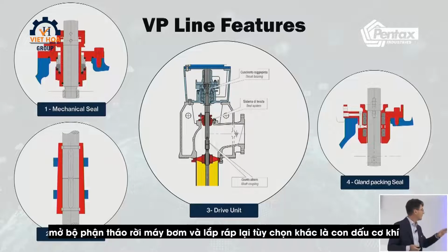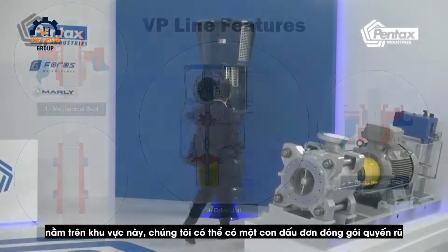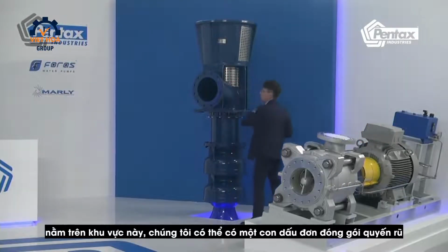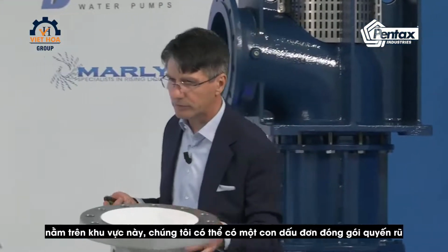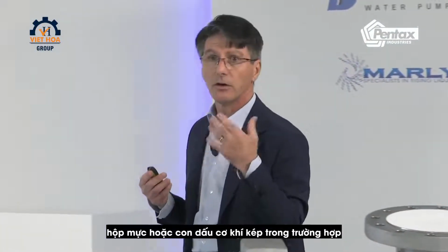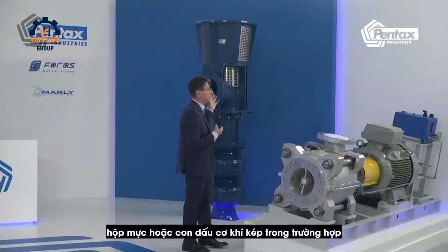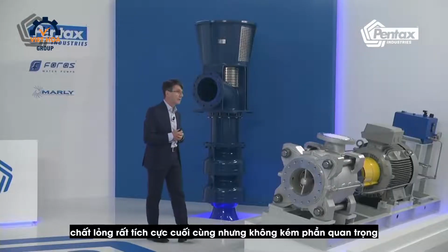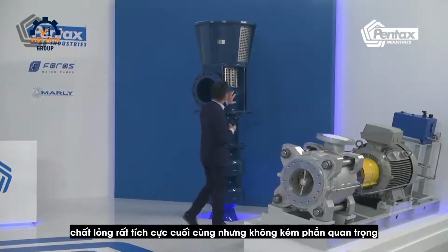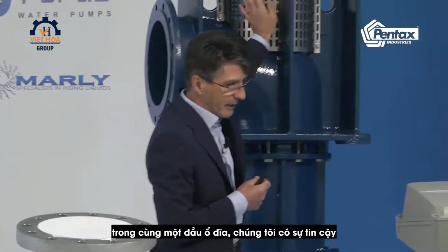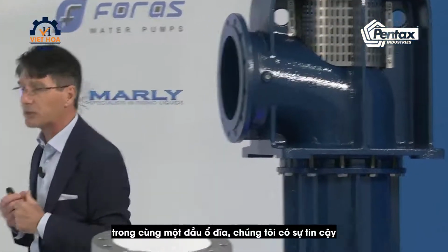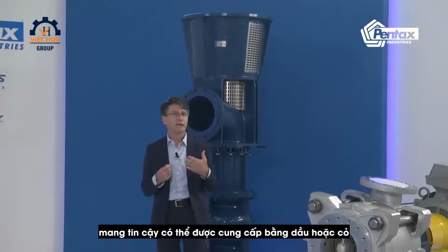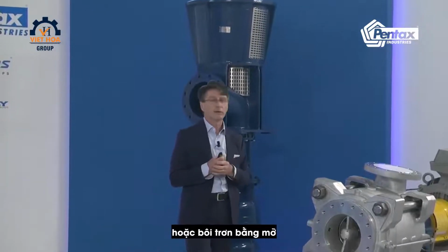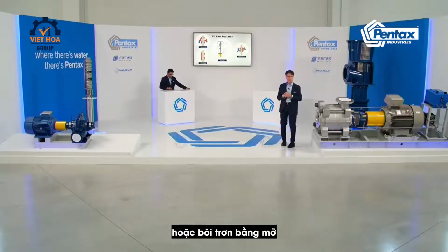Other option is the mechanical seals, which is located on this area. We could have a gland packing, single seals, cartridge, or double mechanical seal in case of very aggressive liquid. Last but not least, in the same drive head, we have the thrust bearing. Thrust bearing can be provided with oil or grease lubrication.